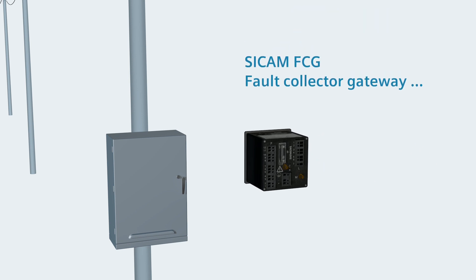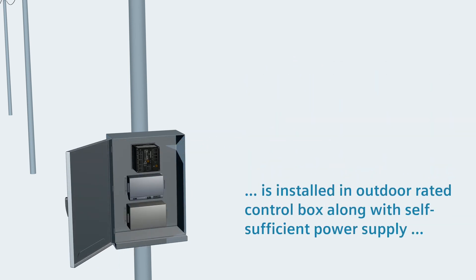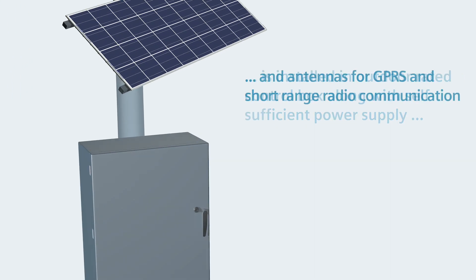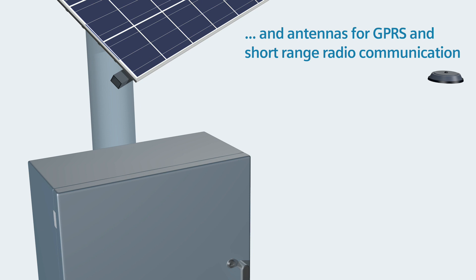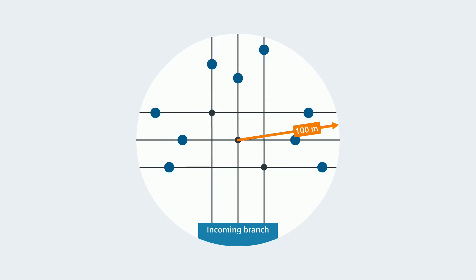As a gateway between SICAM FSIs and the control center or the cloud, you use a SICAM FCG. You install it in an outdoor rated control box on the utility pole along with a self-sufficient power supply. The antennas for GPRS and short-range radio communication are mounted on the control box. A SICAM FCG can collect and process the data of up to nine SICAM FSIs and that up to a distance of 100 meters line of sight.